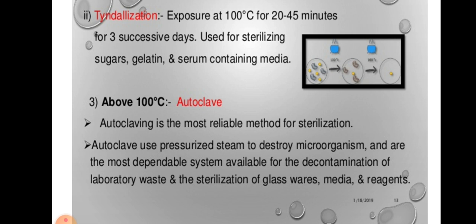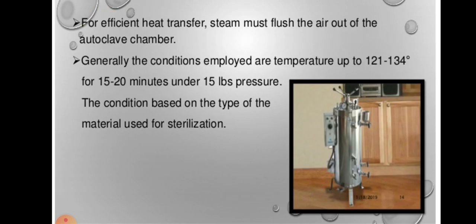Above 100 degrees centigrade is obtained by an instrument known as autoclave. It is the most reliable method of sterilization. Autoclave uses pressurized steam to destroy microorganisms and is the most dependable system available for the decontamination of laboratory waste and the sterilization of glassware, media and reagents. For effective heat transfer, steam must flush the air out of the autoclave chamber. Generally, the conditions employed are temperatures of 121 to 134 degrees centigrade for 15 to 20 minutes under 15 LBS pressure. The conditions depend on the type of material used for sterilization.